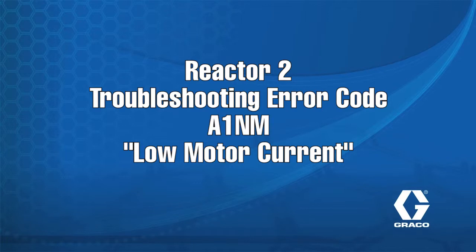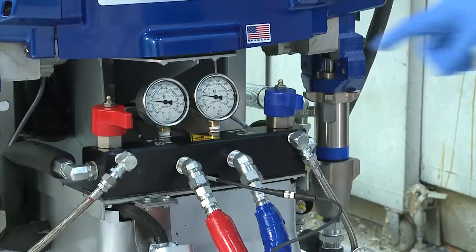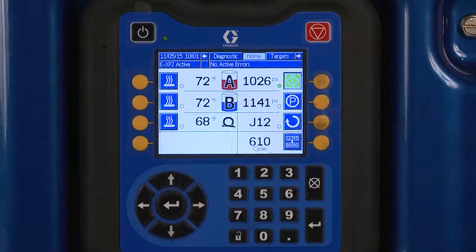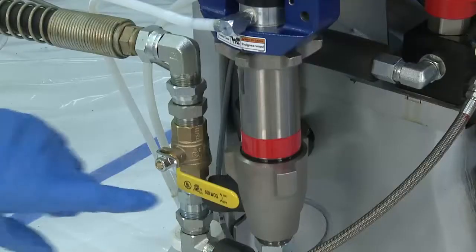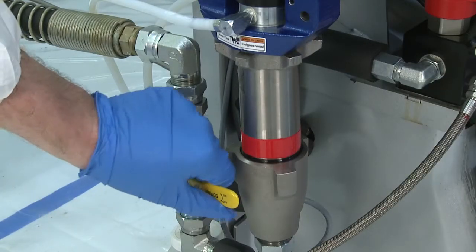The following are possible causes of this error code. Cause 1: Fluid not present in pump. Check for pressure on pressure gauges and the display to verify fluid is present. Also verify fluid inlet valves are open.